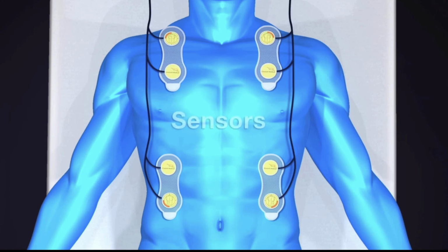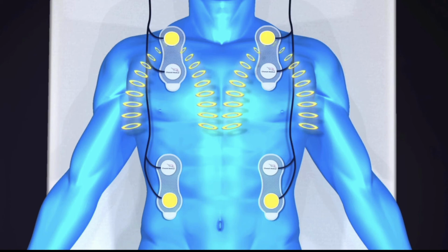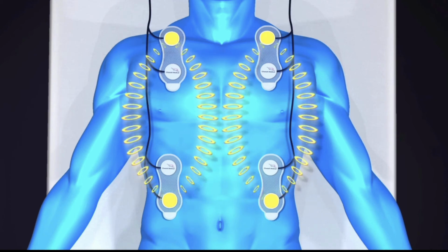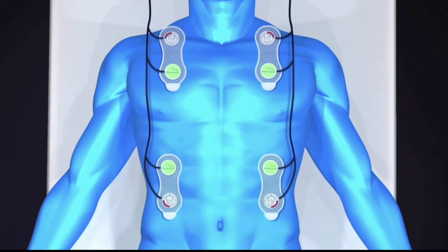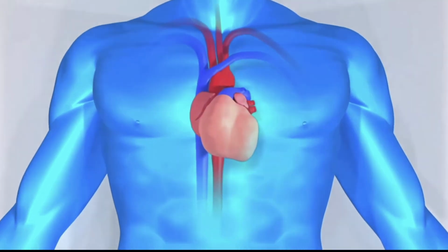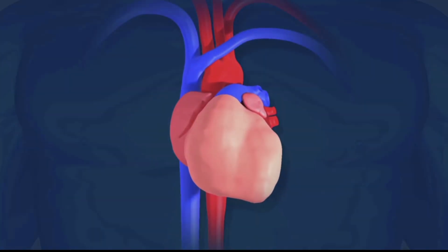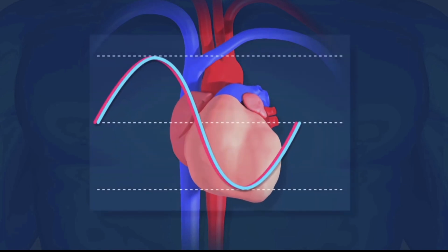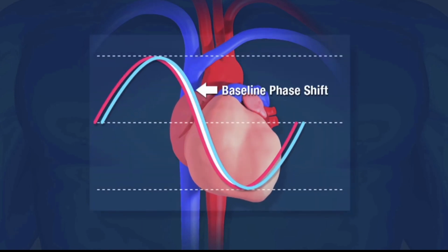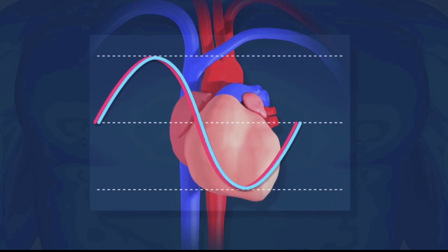The Starling SV has 8 sensors on 4 sensor pads. 4 outer sensors emit a low-level electrical current, and 4 inner sensors detect the information and send it back to the monitor. As the heart expands and contracts, a time delay or phase shift is created in the current by blood flow. The monitor then uses this phase shift as a baseline for measurement.